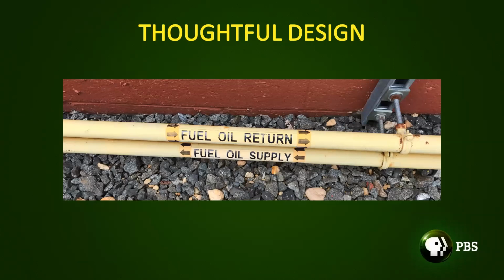This is a shot of the oil lines running from our underground tank — the line on the bottom — and returning to that underground tank. You may ask what that's all about: we actually run the pumps that fill the day tanks on those generators continuously. That pushes fuel into the top of the tank. If the diesels are consuming part of it, only a portion is returned to the supply tank. If the diesels aren't running, all of the fuel is returned to the supply tank.